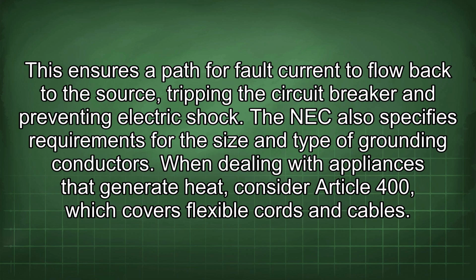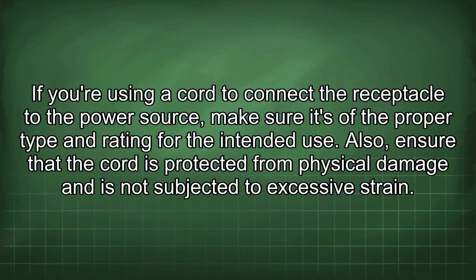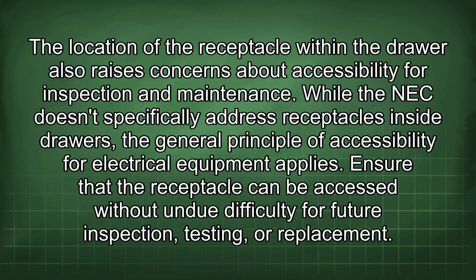When dealing with appliances that generate heat, consider Article 400, which covers flexible cords and cables. If you are using a cord to connect the receptacle to the power source, make sure it's of the proper type and rating for the intended use. Also, ensure that the cord is protected from physical damage and is not subjected to excessive strain. The location of the receptacle within the drawer also raises concerns about accessibility for inspection and maintenance. While the NEC doesn't specifically address receptacles inside drawers, the general principle of accessibility for electrical equipment applies. Ensure that the receptacle can be accessed without undue difficulty for future inspection, testing, or replacement.